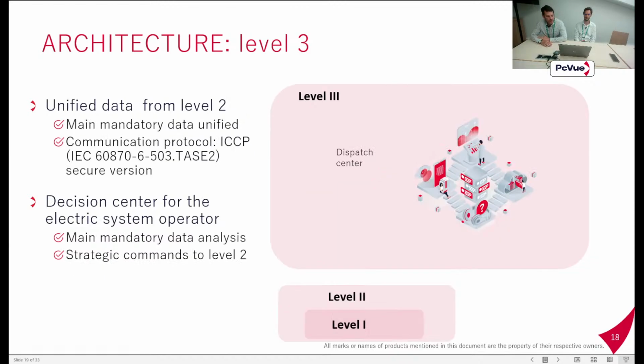Level 3 is the dispatch center - a really critical point that evolves a lot. In Spain, for example, it has to go through a special protocol called ICCP, Inter Control Center Protocol, and it has to be secured. A new version has been available since December, and it evolves every year, so you need to always have the latest protocol homologated by the national grid of the country.